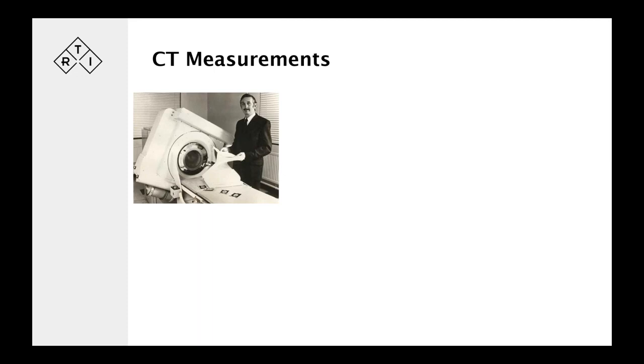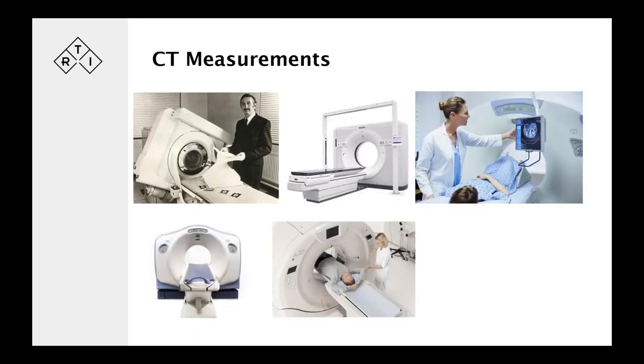Of course, that had some limited functionality, and that has grown over the years, so that we have not only full bore or big bore CT scanners, we also have wide beam CTs, like we see here in this area, where you have a 160 millimeter slice or beam width for that kind of CT, which is becoming more and more common.